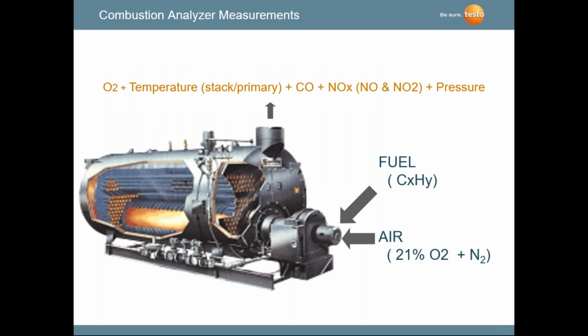And we all understand the design of a boiler. We're taking in fuel, we're taking in air. Air is made up of 21% oxygen. Fuel could be a hydrocarbon fuel, any fuel, propane, natural gas, oil 2, oil 6, and we're producing byproducts. And these byproducts are used in the analyzer. We're sampling in the stack. We're measuring oxygen, temperature, carbon monoxide. We're measuring the NOx, and we're measuring the pressure for stack draft.